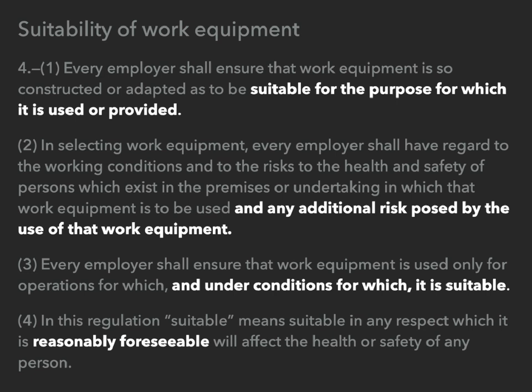When they say suitable, it also includes any reasonably foreseeable effects on the health and safety of the person. So when we say suitable, it's got to take into account dirty filters. When we design systems, we don't design it to run on clean filters because a clean filter isn't cleaned for very long. It's going to get dirty, so it's foreseeable that the filter will get dirty.